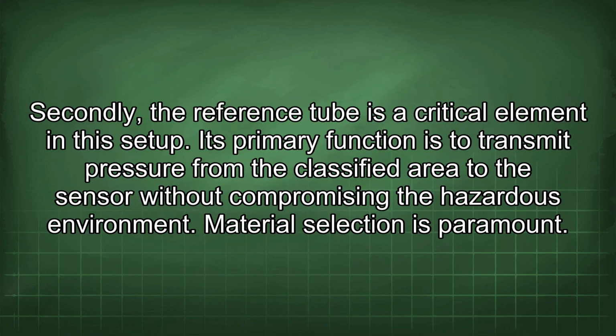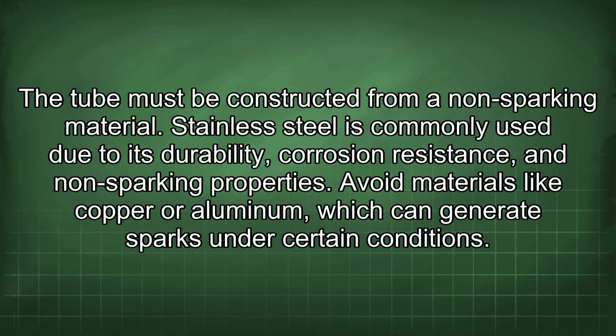Secondly, the reference tube is a critical element in this setup. Its primary function is to transmit pressure from the classified area to the sensor without compromising the hazardous environment. Material selection is paramount. The tube must be constructed from a non-sparking material. Stainless steel is commonly used due to its durability, corrosion resistance, and non-sparking properties. Avoid materials like copper or aluminum, which can generate sparks under certain conditions.